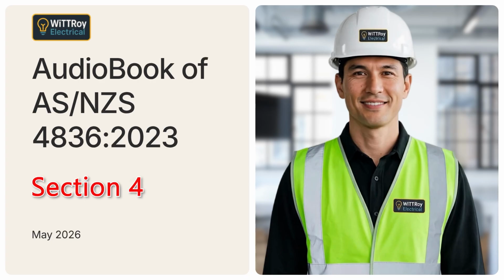They must be proficient in electrical rescue and CPR. CPR means cardiopulmonary resuscitation. They must wear the correct PPE. PPE means personal protective equipment. They must also have ready access to a rescue kit that is suitable for the task. A safety observer must also be able to perform the role properly. If a temporary or permanent condition affects their ability to observe, communicate, or respond, they should not be used for that role. In practical terms, a safety observer is not just another person standing nearby. They are an active safety control. Their attention must stay on the worker, the work area, and the electrical risk.